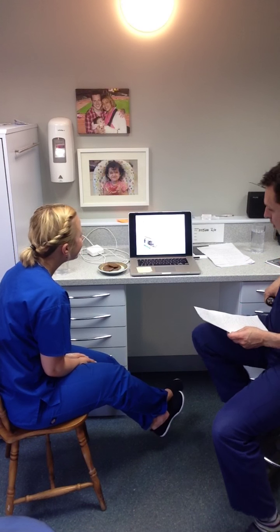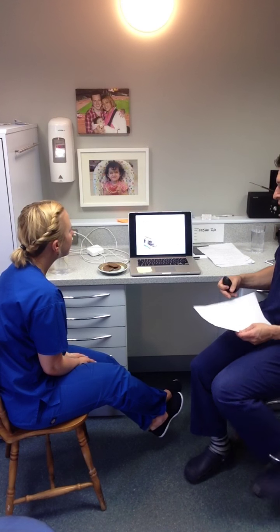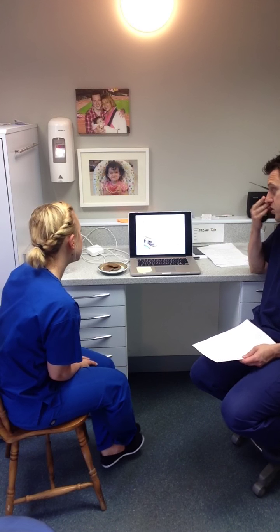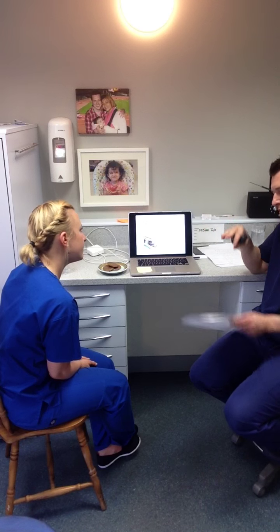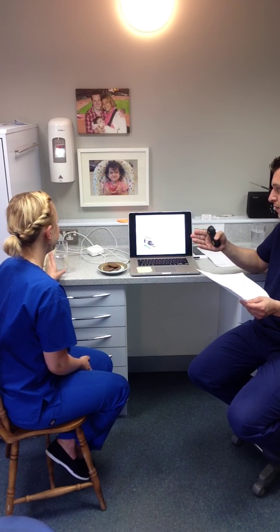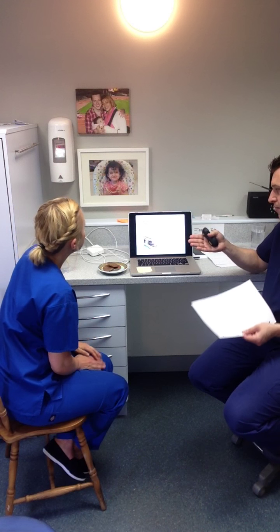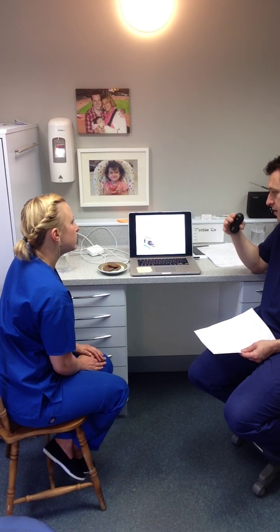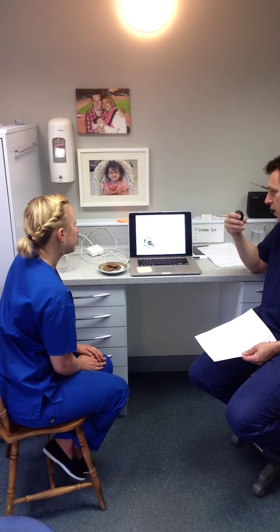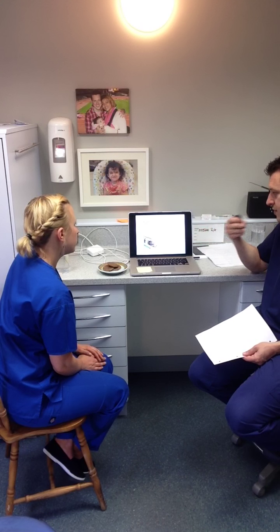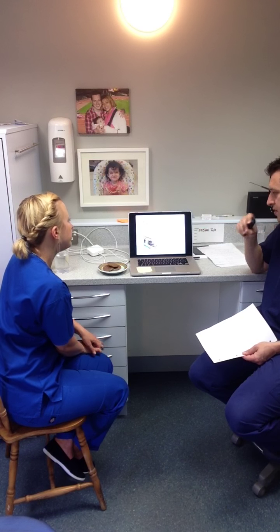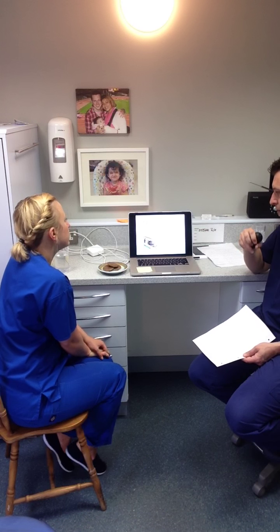So the main overarching document that the Department of Health have come out with is the Health Technical Memorandum 01. That is an overarching umbrella for multiple documents. The one that's relevant to primary dental practice is 01-05. 01-02 alludes to decontamination in laboratories. 01-03 is decontamination in pharmacies. But Section 5 is specifically about primary dental practice.